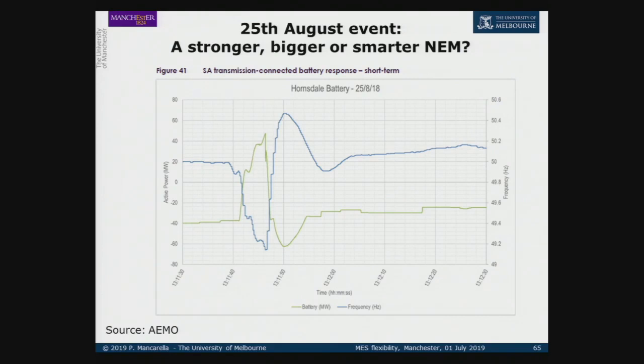What was the battery doing in South Australia? Look at the green trace - this is the battery. The battery is effectively following the frequency, mirroring it. There is a droop control of the battery with an activation delay of about 0.2 seconds, and then it basically mirrors the frequency. The frequency goes down, touches some thresholds, the battery responds, and the green mirrors the blue. Then the frequency goes up, and the green goes down as a mirror.